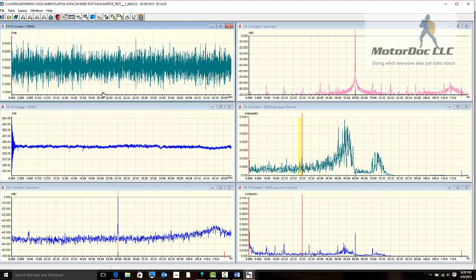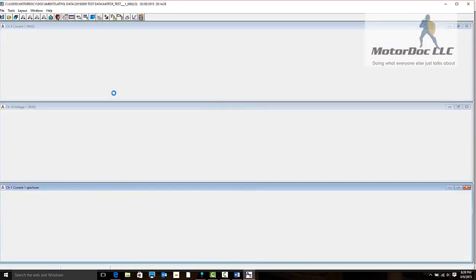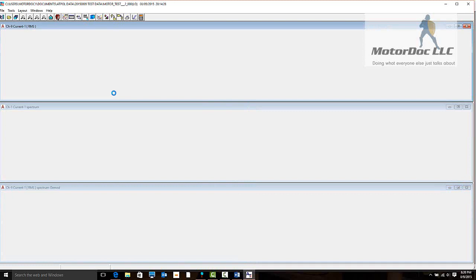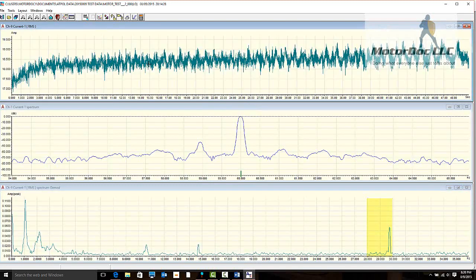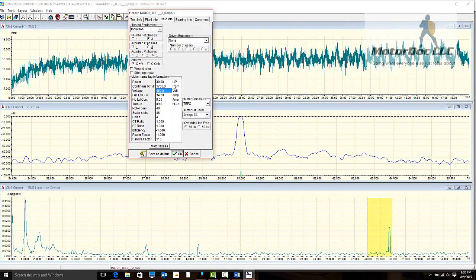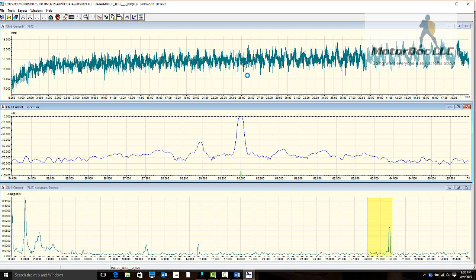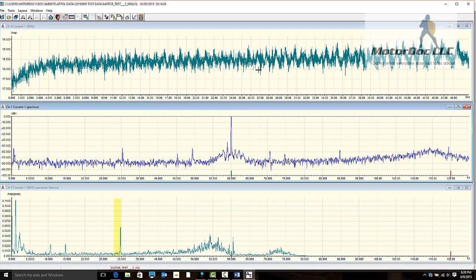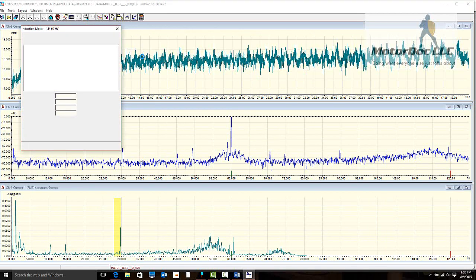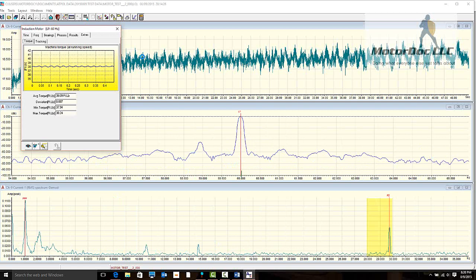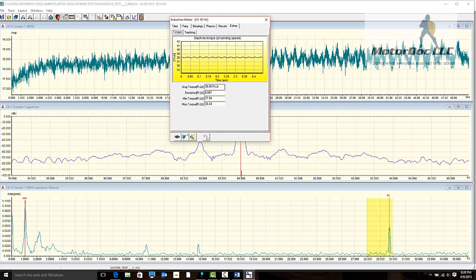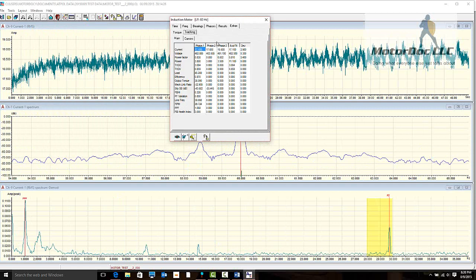Let's take a look at a second one. When we open this up, we're going to see that we have, at 50% load, I have all my nameplate in here. I can take a look at that spectrum. This is at 50% load. You notice some additional peaks. At 50% load I can now look in here and let's see what we find. Here we go. This is where I was before. This is my torque reading. This is all that other information we talked about.